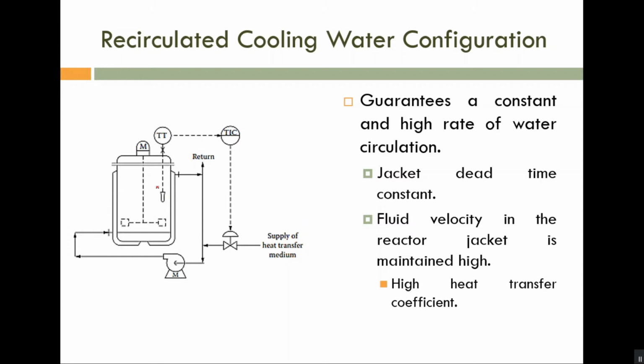If temperature is large, then in order to remove that much energy, we have to increase the flow rate by opening this control valve. This is a normally open valve. In order to open it, we have to give a minimum control signal. If you have large temperature, it means error is negative, means small error. So for small error, small control signal, the valve is open, so flow rate is increased, and vice versa. It is similar to what we discussed in the last class.